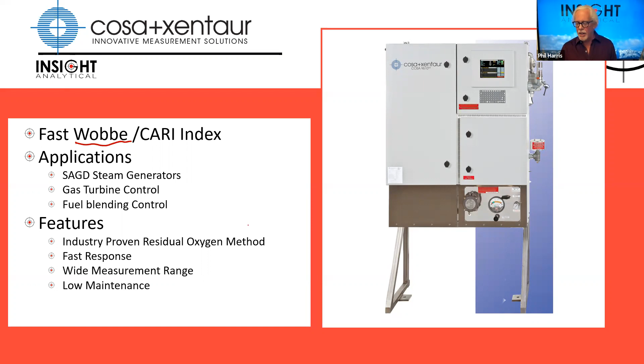A big feature about this is it's an industry proven method - probably the most accepted method for doing wobbe index is this residual oxygen method. It gives us really fast response, has a wide measurement range, and low maintenance compared to some other methodologies. What we really do is take a sample, burn it, see how much oxygen is consumed, and from that we correlate how it's going to burn once it gets into my steam generator or turbine.